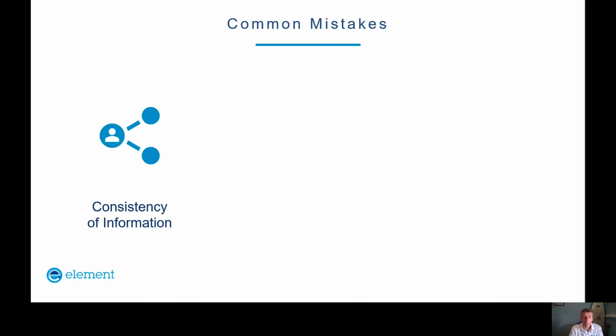Some common mistakes then. Consistency of information. Often products come to me as a notified body or UK approved body for a review where somebody has installed a radio module and they've said, we only did this test because it was the worst case. Well, then when you look at the results from the radio module, you realize it wasn't the worst case at all. Maybe it made a guess, or the statements from the final installer don't match what the module originally did, and nothing seems to align.